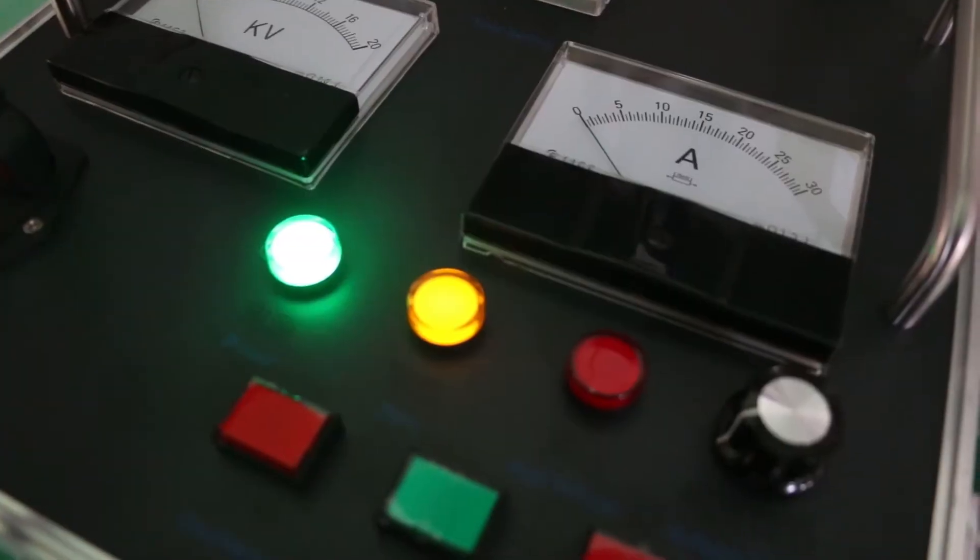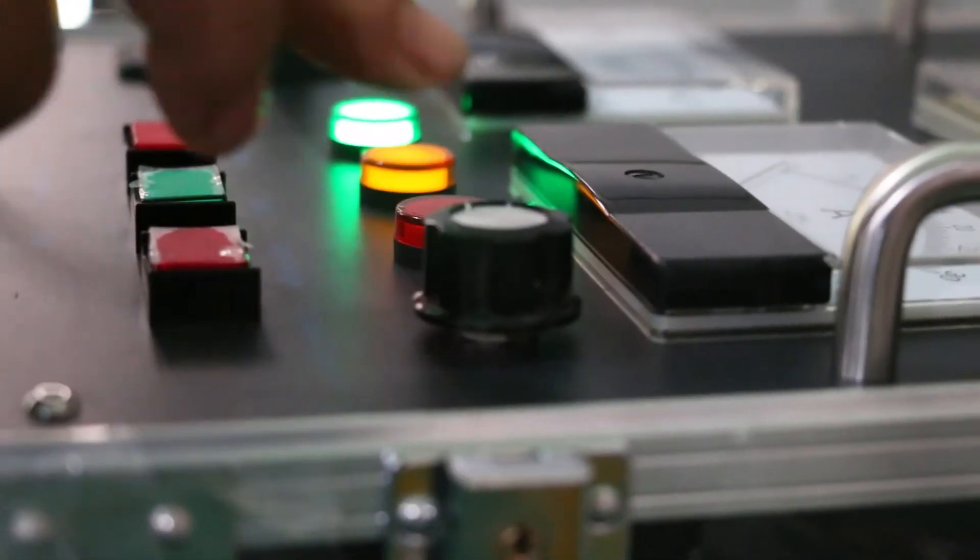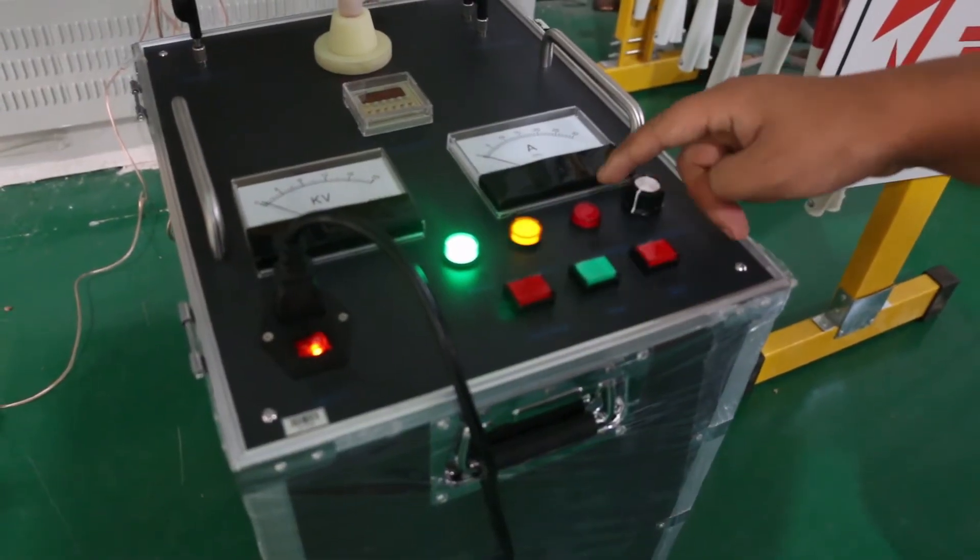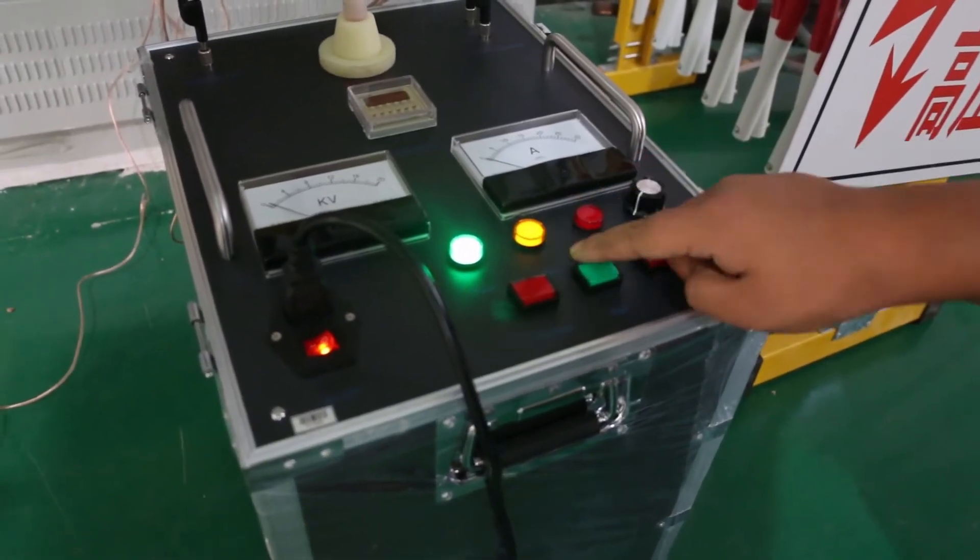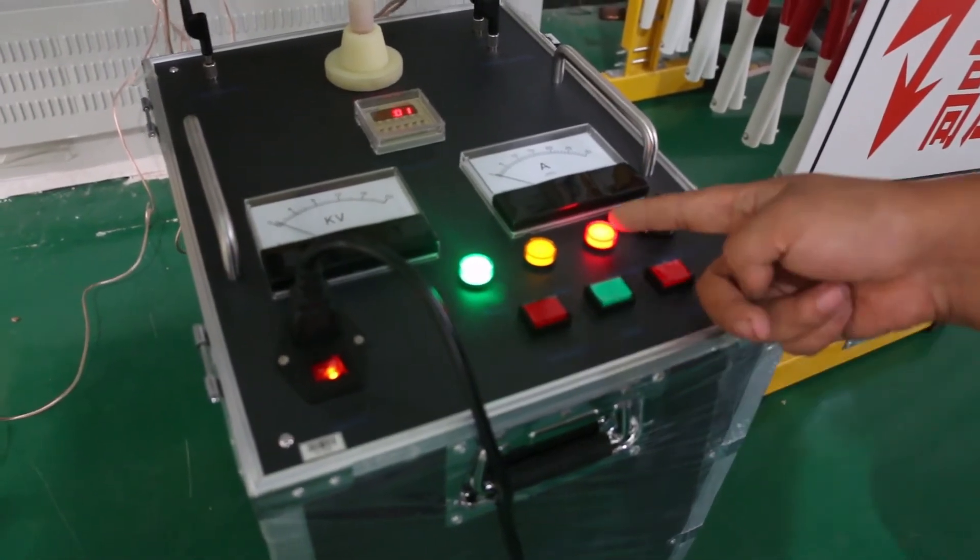Second, power indicator will light up after turning on the generator. Turn the voltage regulator anti-clockwise to the end until it can't be turned. The zero indicator will light up. Press start button and the high-voltage indicator will light up.